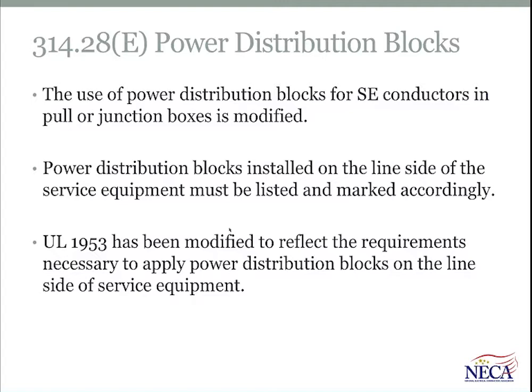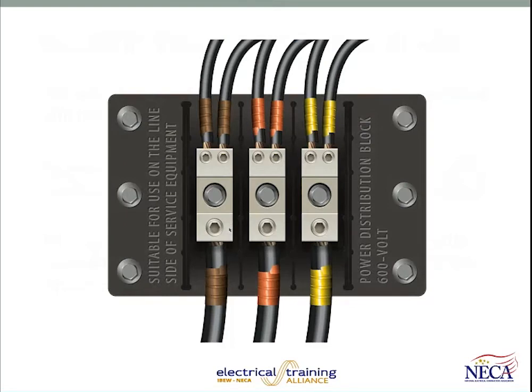Remember that the amount of available fault current from the serving utility is typically a lot higher than if it were on the load side of an overcurrent protective device, and that's going to have an impact on the listing, evaluation and marking of a power distribution block that is intended for use on the line side of the service equipment. The graphic just shows an example of a power distribution block. This one has the guards removed. Remember that when these things are used in actual field conditions, the completed installation would include a shield or a guard over those live parts.